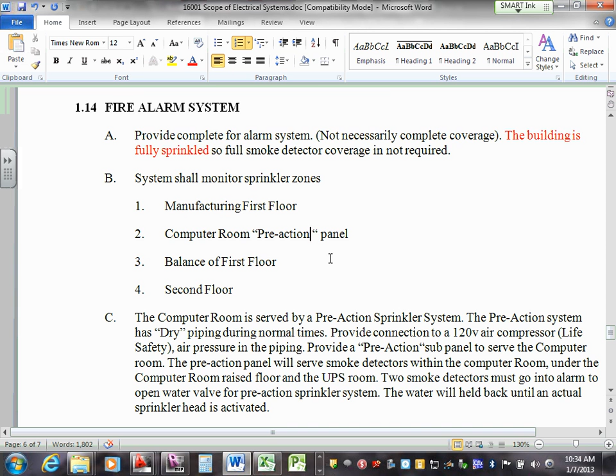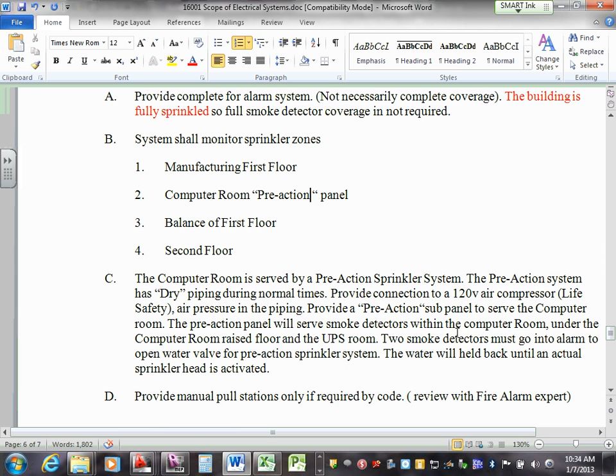I don't want to take the flair out of Matt's presentation, but he's trying to introduce you to the fact that there are still times when we do full coverage, especially in our data center world, where we may put in a full, even complex, detection system because we don't have wet sprinklers in the room. We have dry pipe, with valves that shut the water off, so now we have full detection coverage. That detection system would actually open valves and allow water to come in as a last resort.